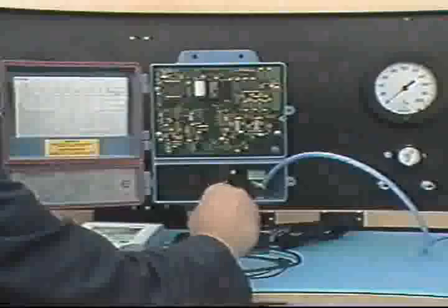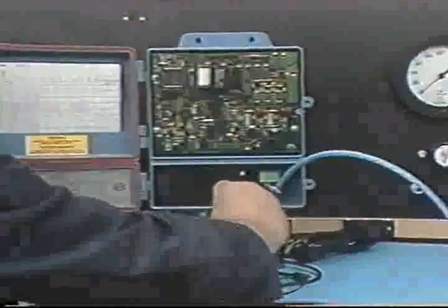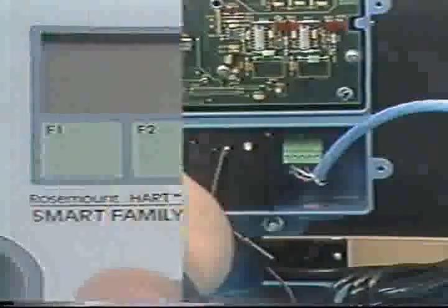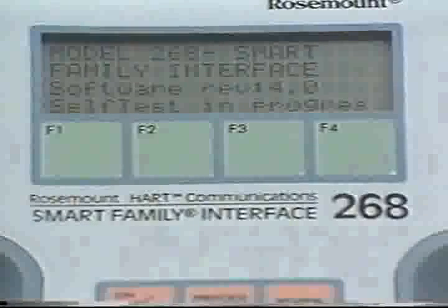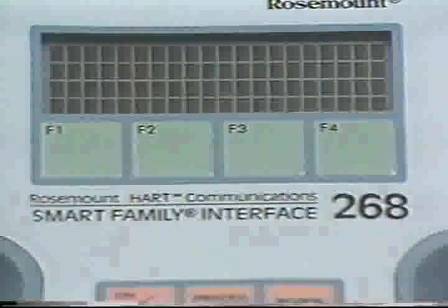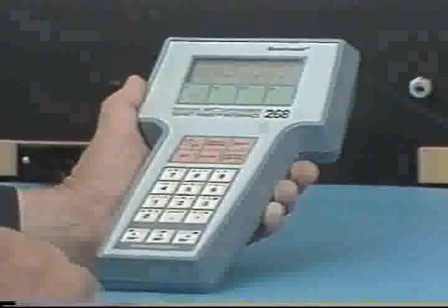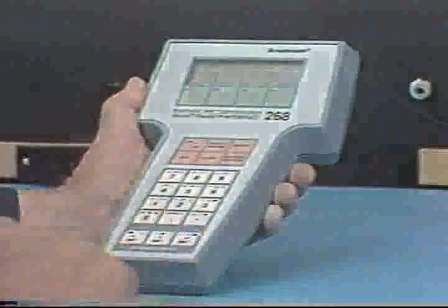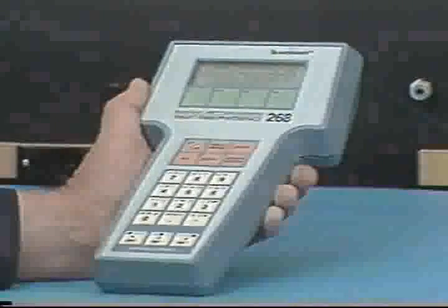Now that we understand more about the interface device, let's see how it's used to configure the transmitter. Configuration defines the parameters of the transmitter's operation. When the interface device is turned on, a self-diagnostic program checks to ensure the device is working properly. Pressing the Config key will begin configuration. Then enter information to identify the instrument. The parameters are checked and displayed by the interface device. You can then make changes or proceed with the configuration.